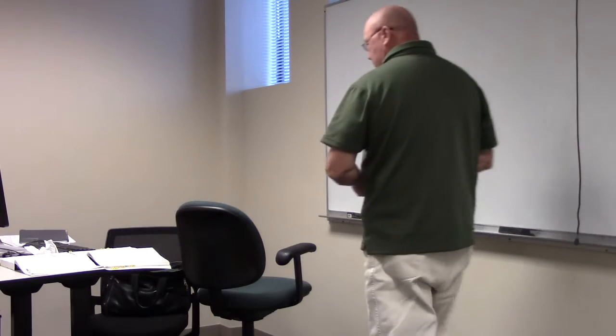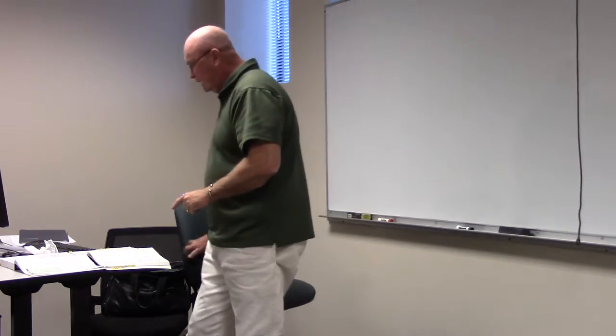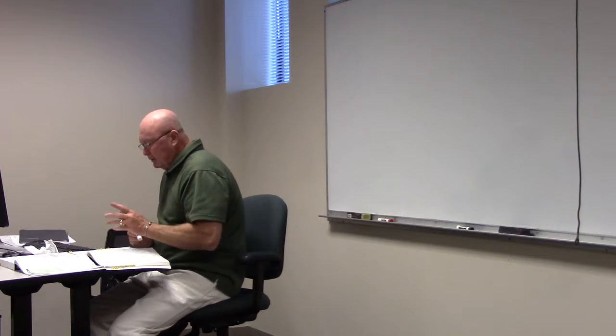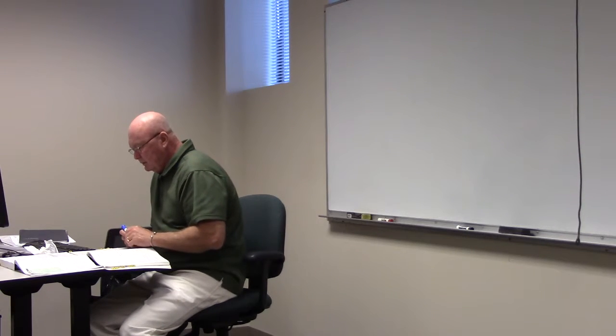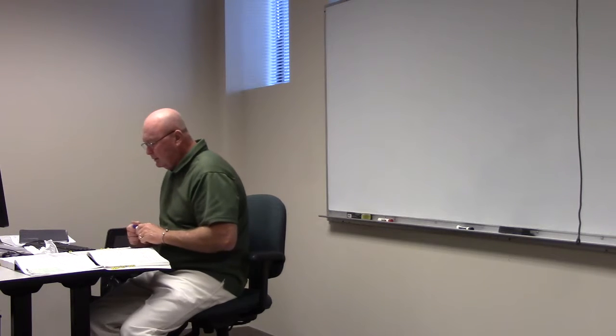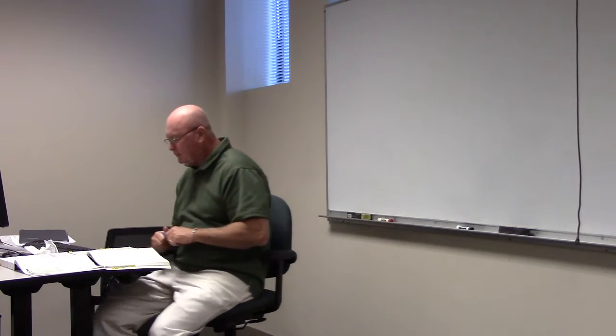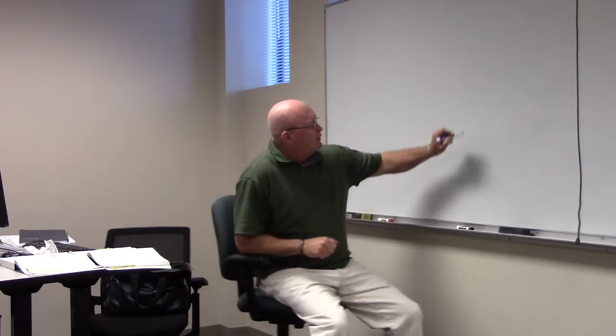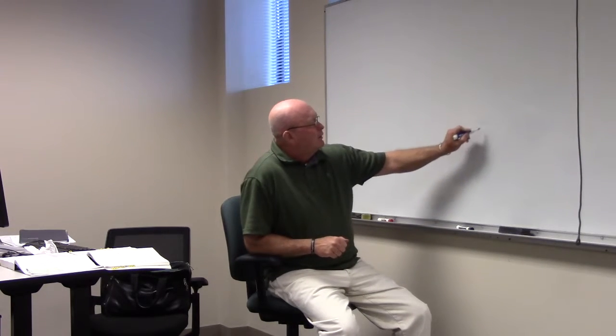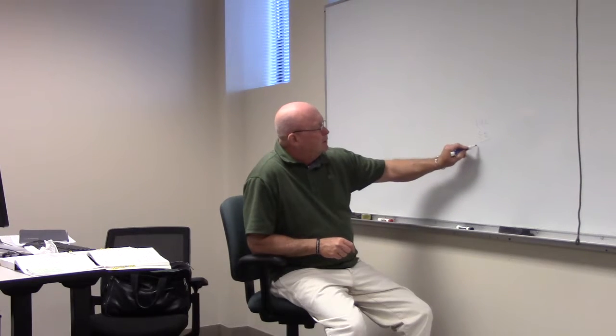All right. Show windows, the next one, track lighting. Track lighting is allowing 150 VA for every 2 foot. So it says we got 140 foot of track. So what are we gonna do? 140 foot? So every 2 foot, we just gotta find out what? We need to divide this by 2, don't we? Yes, sir. So now we got 70 foot that we're doing times what?